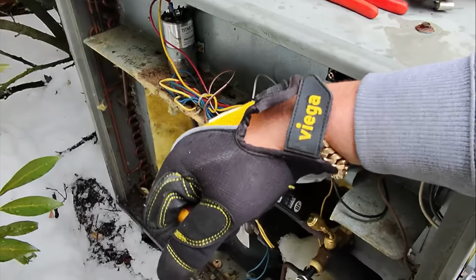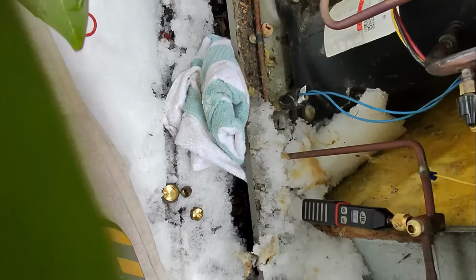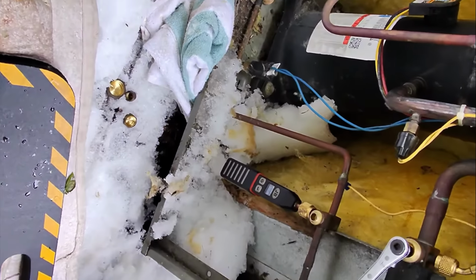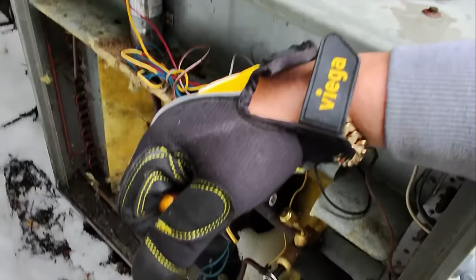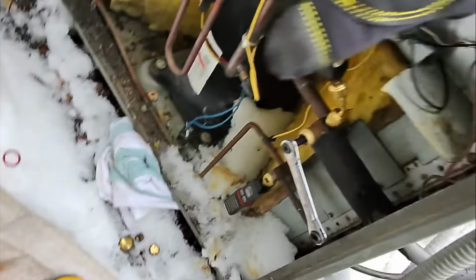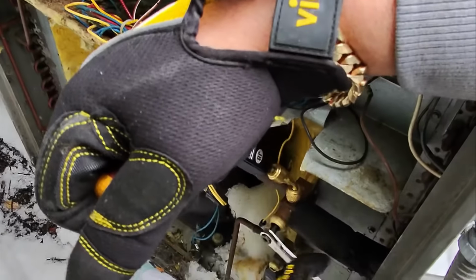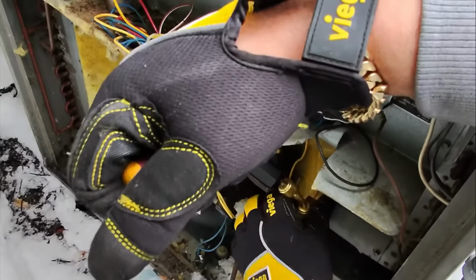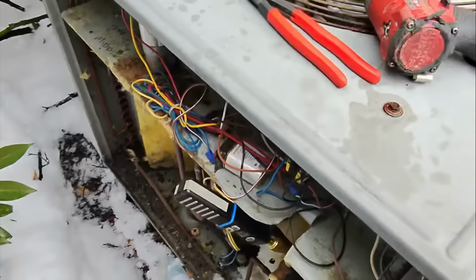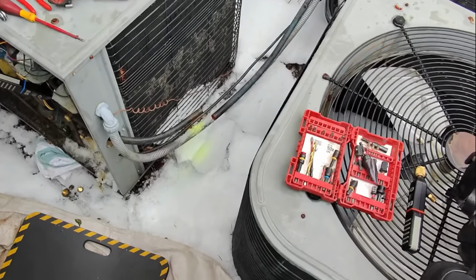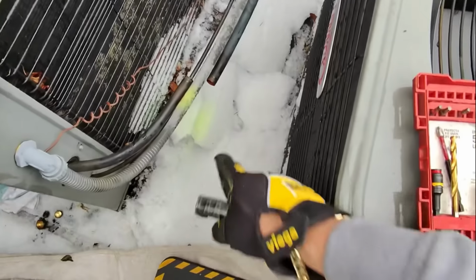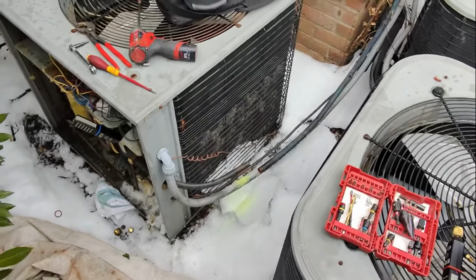All right, now we are at 0 psi. Let this run for a little bit longer. Negative 2.2 psi. All right, let's close this. And now we have pumped down the refrigerant into the condensing coil. Loose there. Okay, that's it. Cut the line set and look at all of that yellowish green. That's the dye. Someone added dye to the system before to look for a leak. We're gonna have to flush that out.